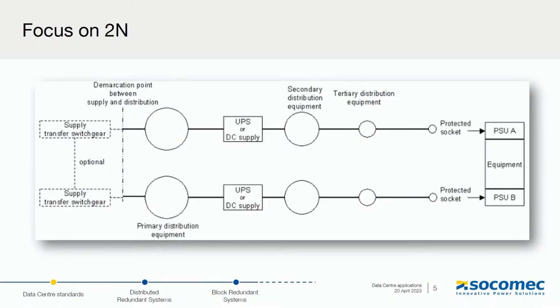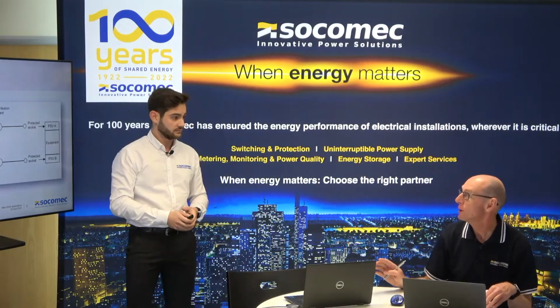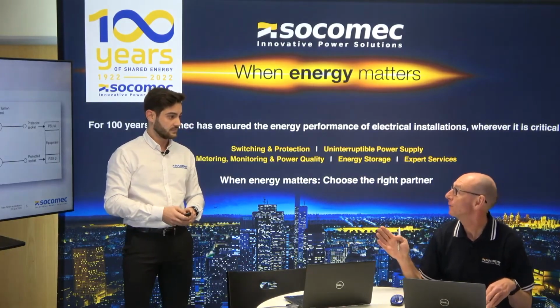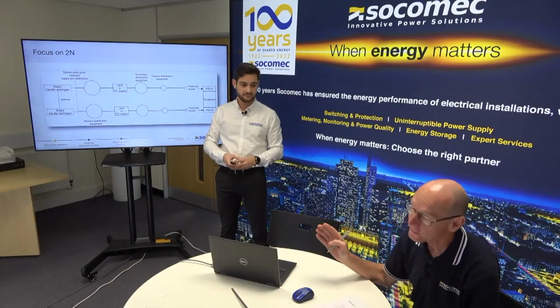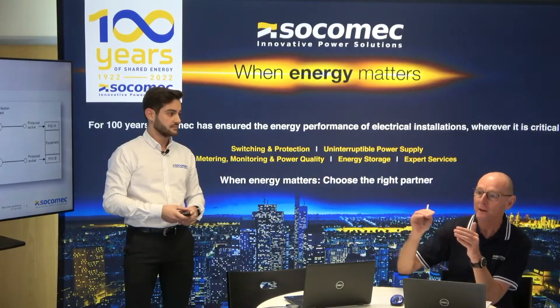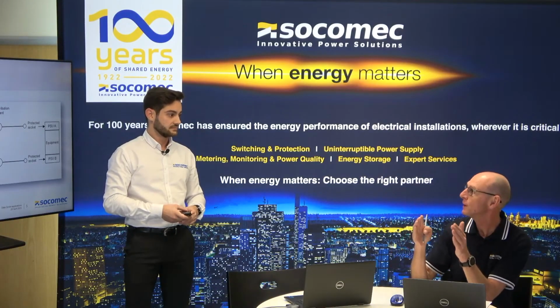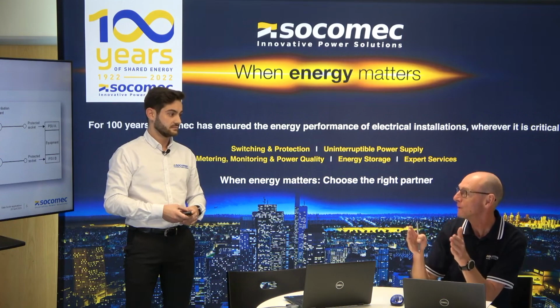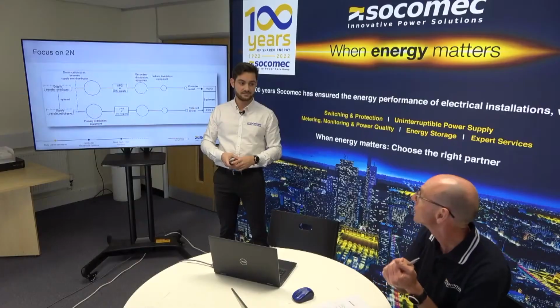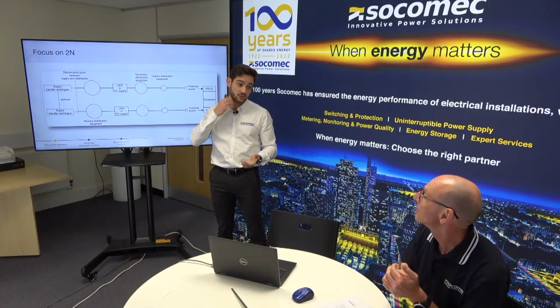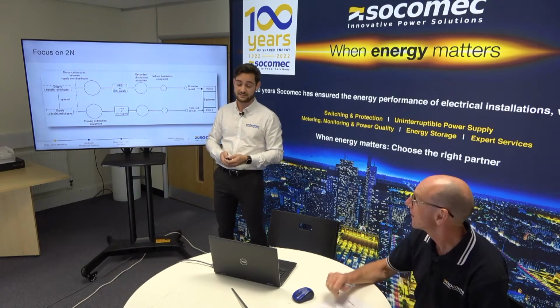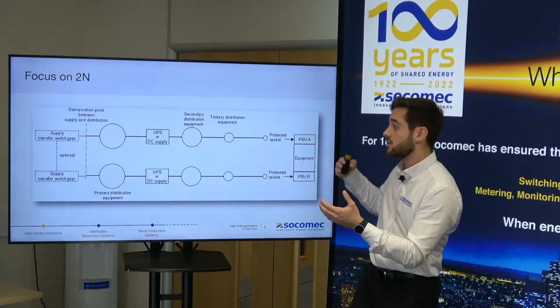And obviously during normal operation, those UPSs are only going to be running at a maximum of 50% of load, which is why I think you will have seen over the years the efficiencies of data center UPSs, where it used to be up at 80-90%, they've changed the curve now to make them more efficient at the lower usage, so around the 50%, because that's typically where they're being used. And which is really important when we think about cost, actually. Exactly, yes. Right. That's the example of the diagram.